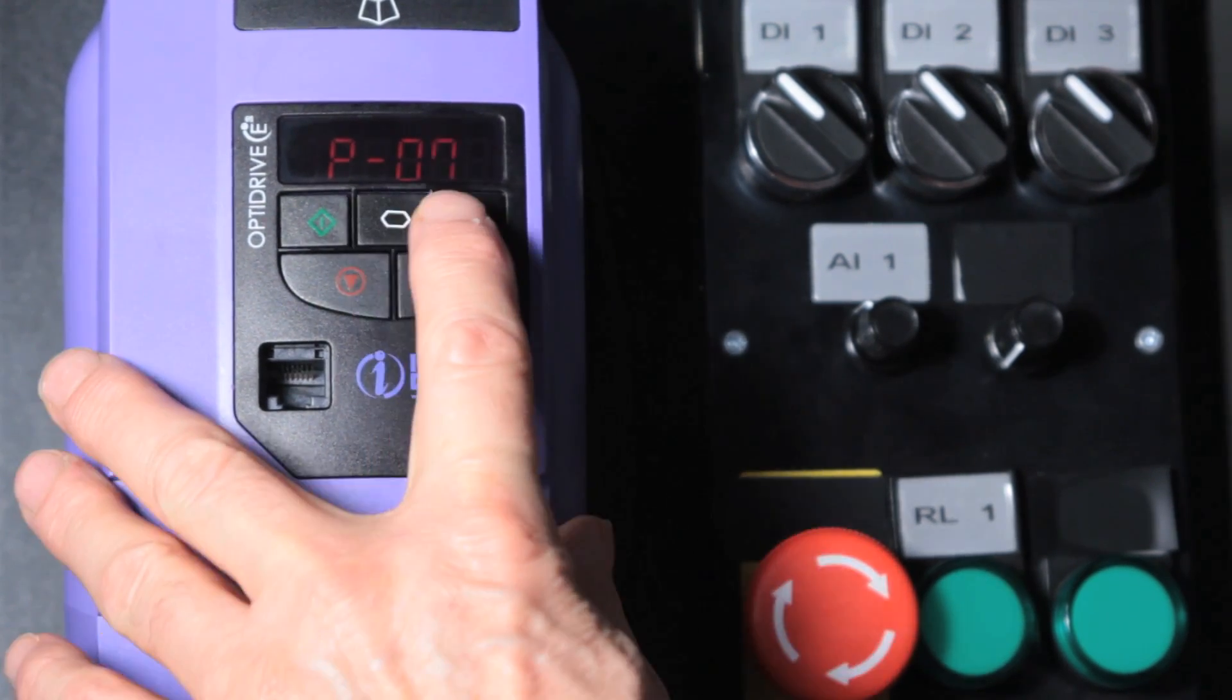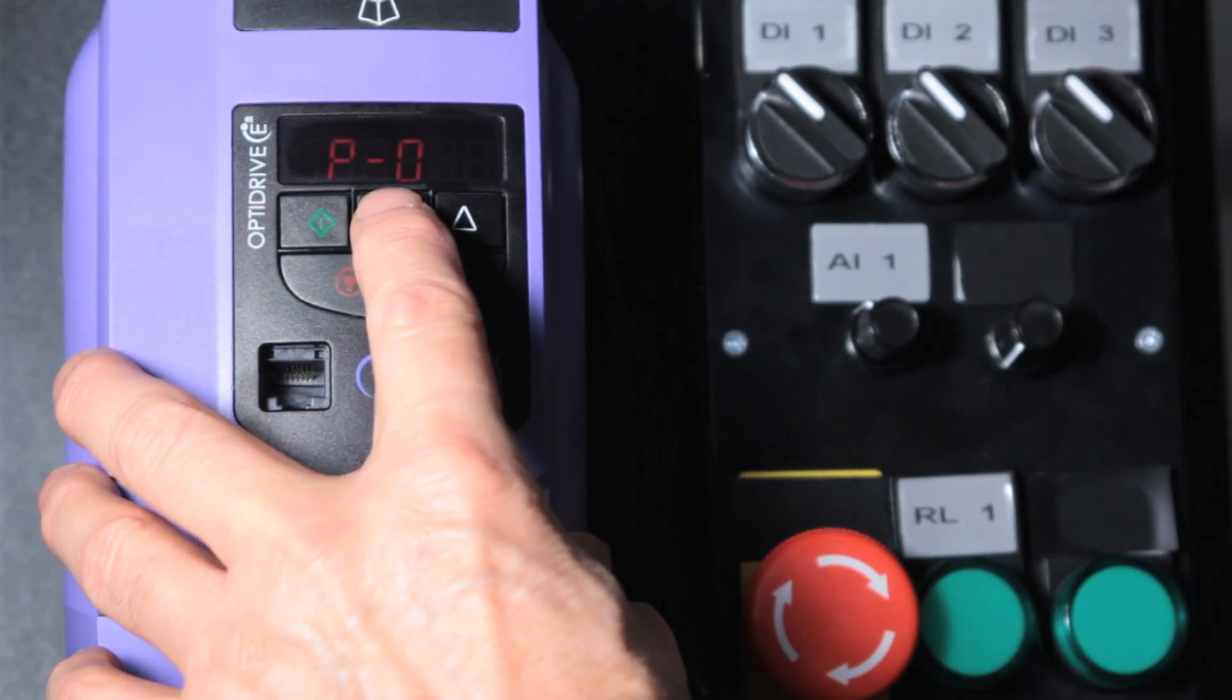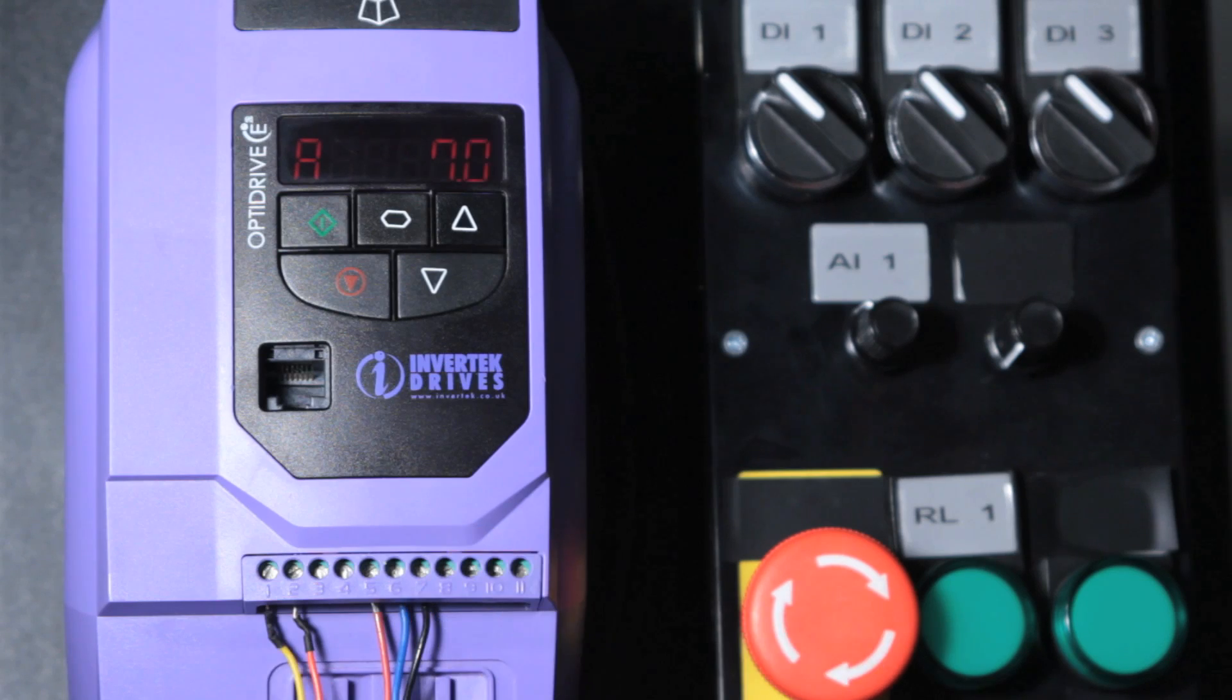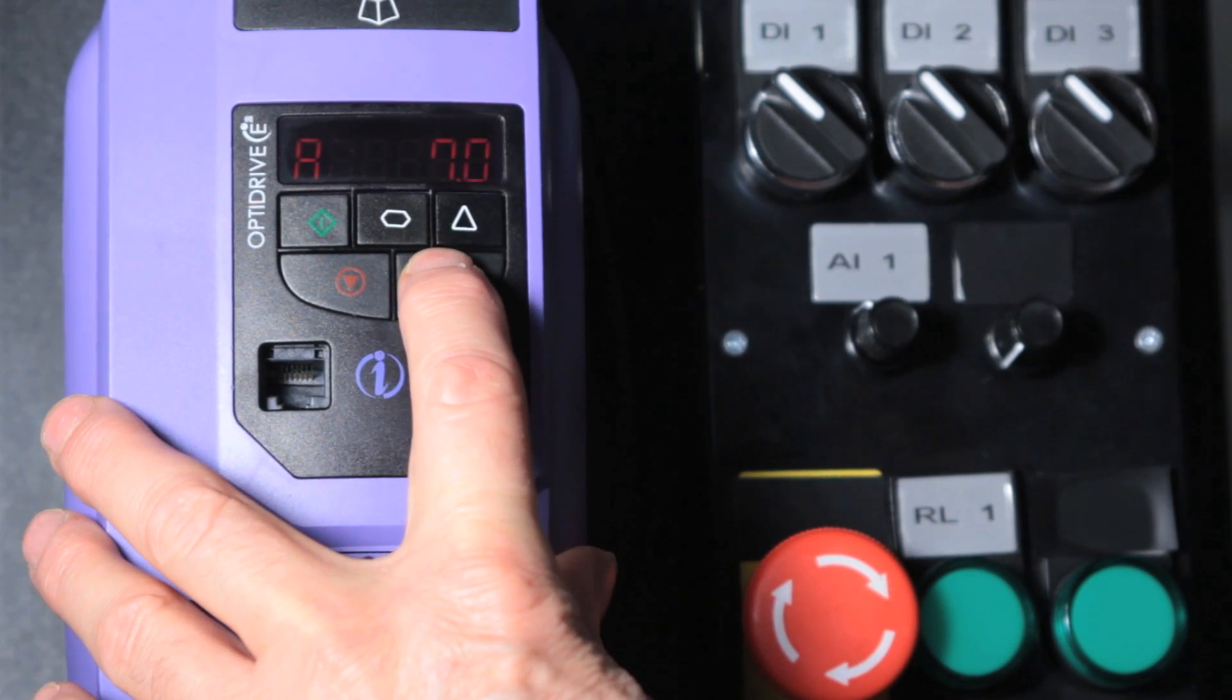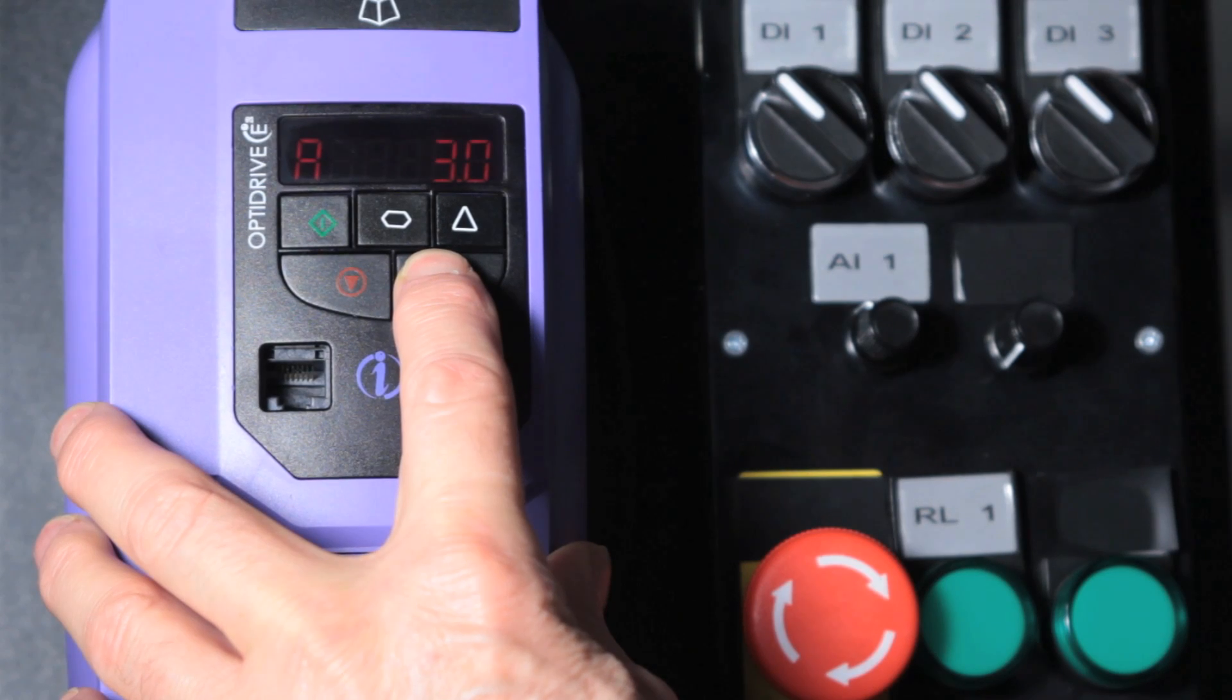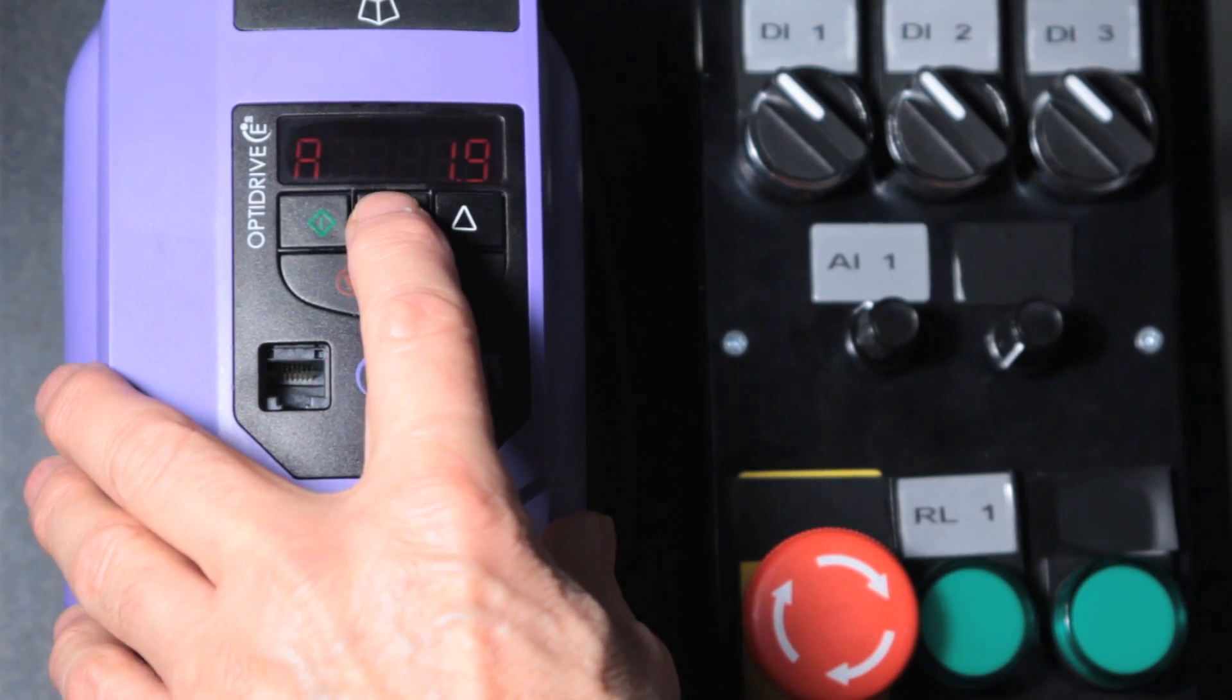Short press back to parameter then scroll to parameter 8. Here's the motor current now. We need to adjust this to a lower value to help protect the motor. This motor is a 1.9A motor.